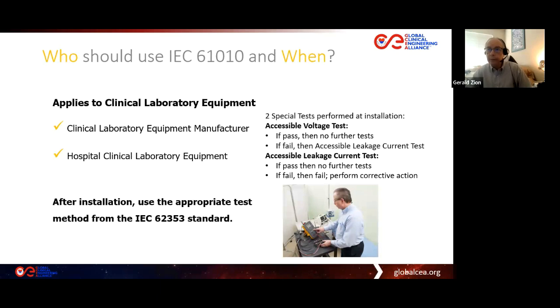All right, there's another standard out there that is often confusing to everybody internationally, and that is the IEC 61010. Well, the IEC 61010 is really not just about medical devices. It is an international safety standard applied to all kinds of things, including the test equipment that we use. It has been adopted by the pathologists who control the requirements for clinical laboratory equipment. And the 61010 has only two tests that are unique for this application, for the analyzers and analyzing systems used in the clinical laboratory. They are the accessible voltage test, and this is an if-then-else logic.